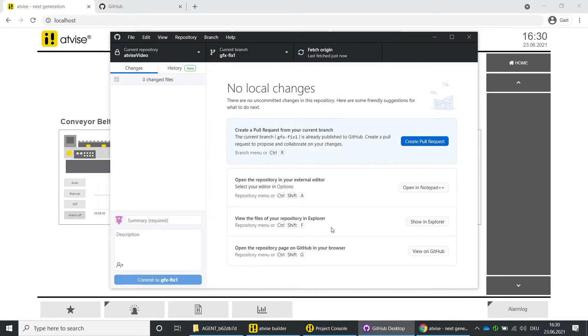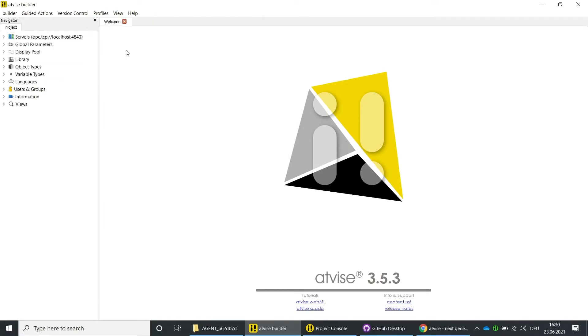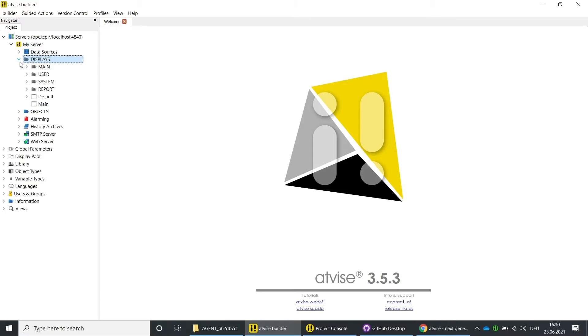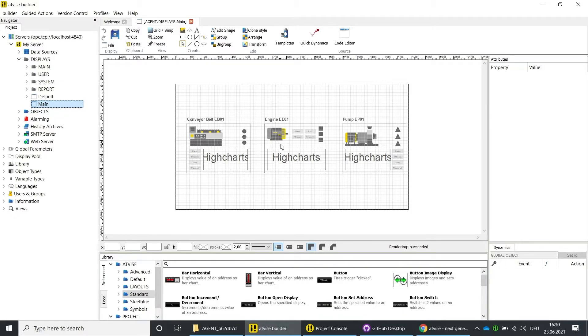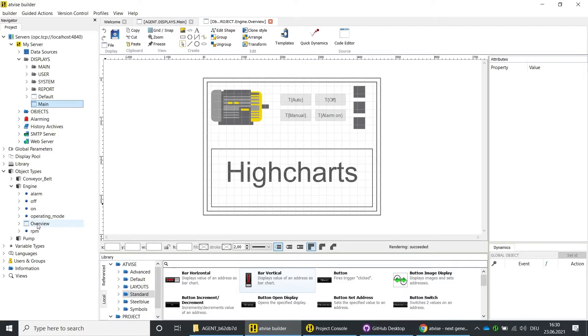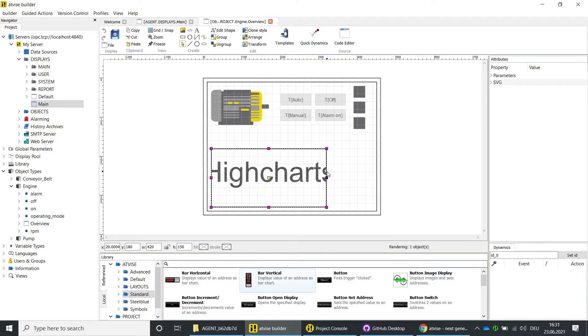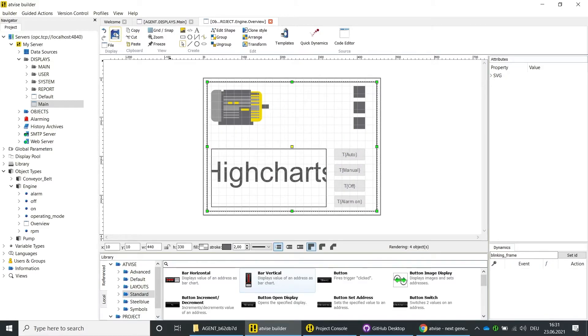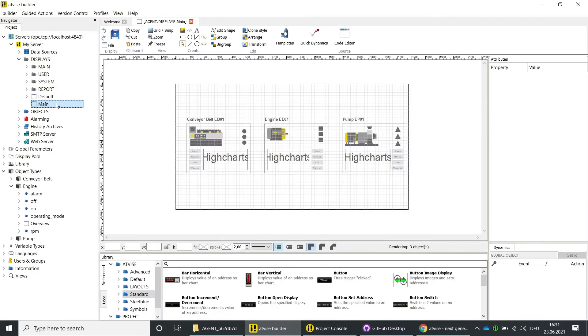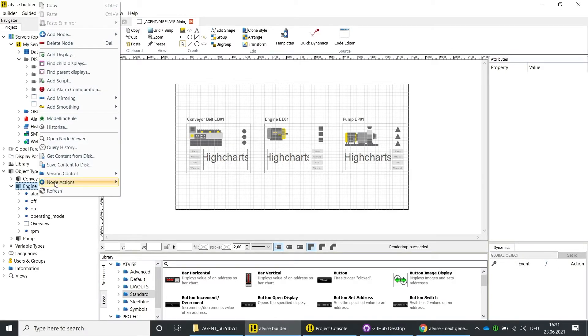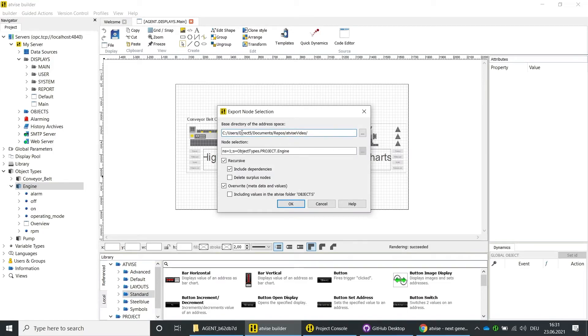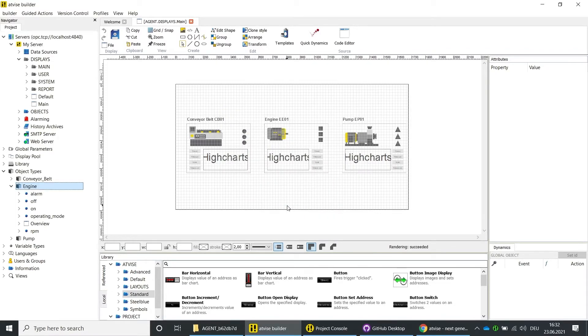Open the atvise Builder and close the node browser. Open the main display. Open the reference display of the object by right-clicking on the object and clicking on Edit Referenced Display. You can also find the display in the project structure under Object Types Engine Overview. Move the elements based on the requirements of the customer and save the display. Close the main display and open it again to ensure all changes take effect. Because just parts of the project have been changed, we will export just a subtree. Right-click on the object and go to Version Control, Export Nodes. The base directory is already filled and the node selection shows just the selected object — all underlying objects will be exported recursively. Click on OK to start the export.